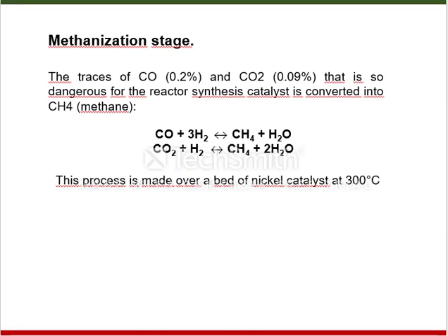Methanization stage. The traces of CO and CO2, which are so dangerous for the synthesis reactor catalyst, are converted into CH4, that is methane. This process is made over a bed of nickel catalyst at 300 degrees.